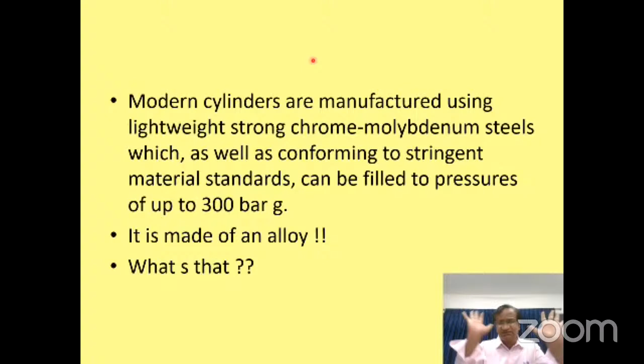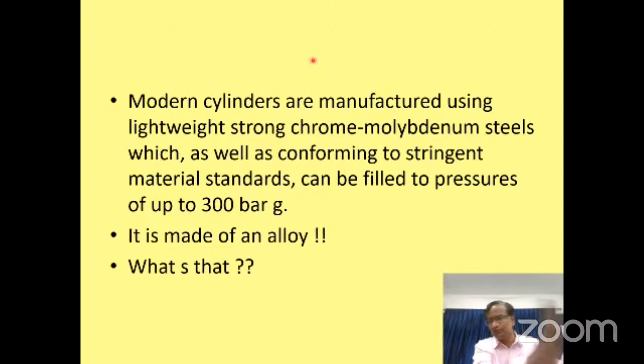Modern, we will go to the anesthesia part and not other gas cylinders. And we will orient more towards oxygen and less towards other gases. Okay. So modern cylinders are manufactured using lightweight, strong chrome molybdenum steel. Its weight is less, but it is strong. As well as conforming to stringent material standards, it can be filled up to 300 bars. So I have already told you it is made up of an alloy. Okay. Alloy means mixture of metals.